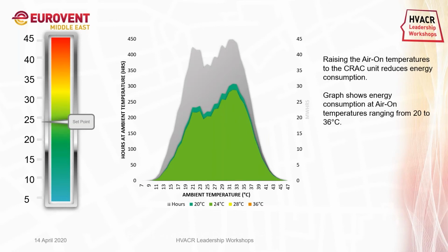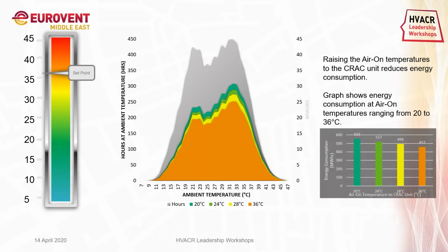While we increase the set point to 24 degrees Celsius, the energy consumption reduces. At 28 degrees Celsius, it further reduces. And at a set point of 36 degrees Celsius, it reduces further. The set points given, 20, 24, 28, and 36, are the set points of the CRAC unit. Now we have plotted the energy consumption in units at these four air-on temperatures. At 20 degrees, that is 553 units; at 24, that is 517; at 28, it's 494; and at 36, 457. You can see the reduction in energy consumption while increasing the air-on temperatures.